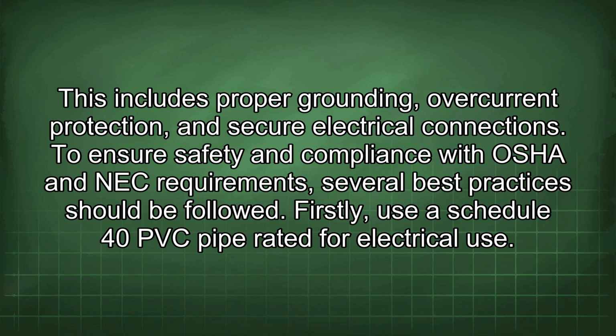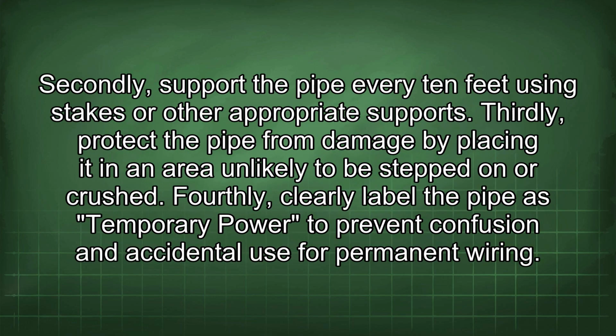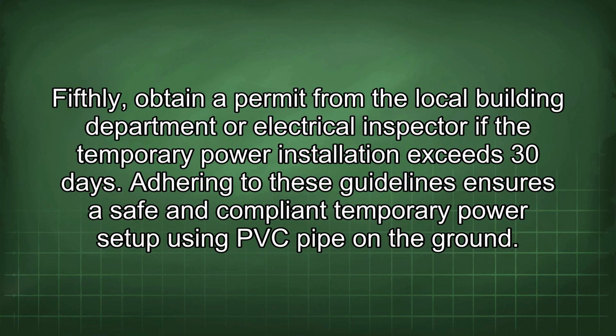Firstly, use a Schedule 40 PVC pipe rated for electrical use. Secondly, support the pipe every 10 feet using stakes or other appropriate supports. Thirdly, protect the pipe from damage by placing it in an area unlikely to be stepped on or crushed. Fourthly, clearly label the pipe as temporary power to prevent confusion and accidental use for permanent wiring. Fifthly, obtain a permit from the local building department or electrical inspector if the temporary power installation exceeds 30 days. Adhering to these guidelines ensures a safe and compliant temporary power setup using PVC pipe on the ground.